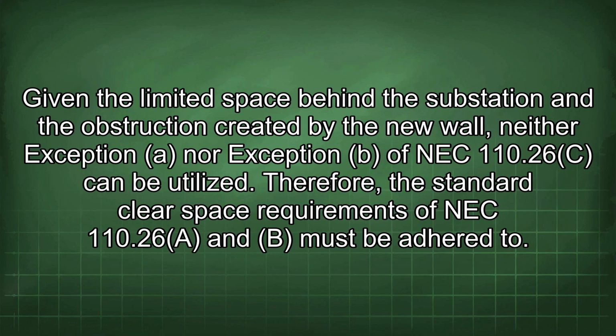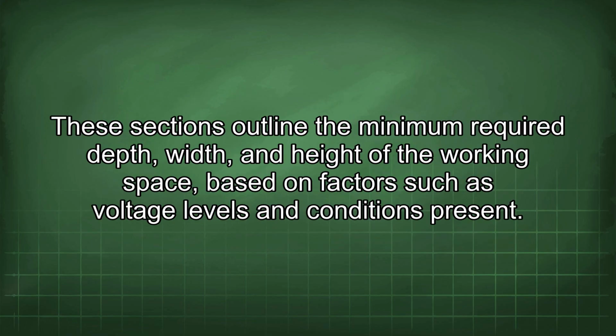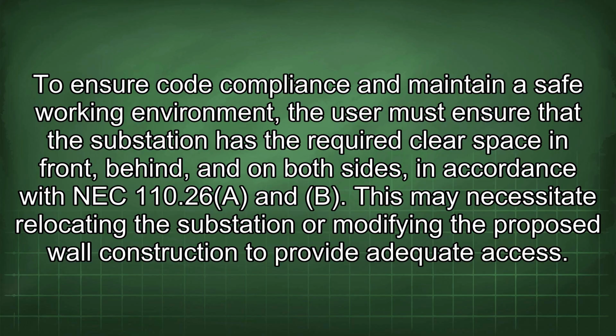Given the limited space behind the substation and the obstruction created by the new wall, neither Exception A nor Exception B of NEC 110.26(C) can be utilized. Therefore, the standard clear space requirements of NEC 110.26(A) and (B) must be adhered to. These sections outline the minimum required depth, width, and height of the working space based on factors such as voltage levels and conditions present. To ensure code compliance and maintain a safe working environment, the user must ensure that the substation has the required clear space in front, behind, and on both sides, in accordance with NEC 110.26(A) and (B). This may necessitate relocating the substation or modifying the proposed wall construction to provide adequate access.